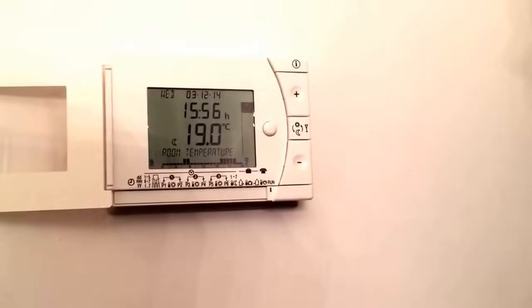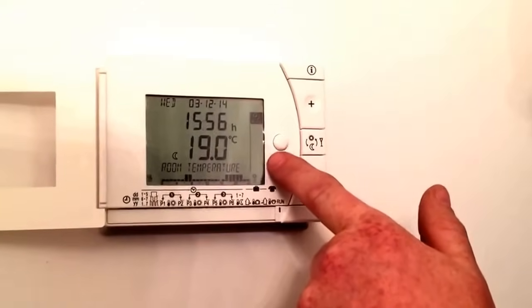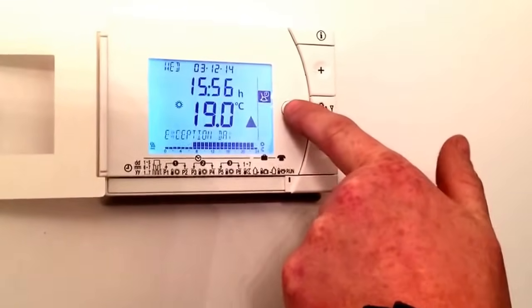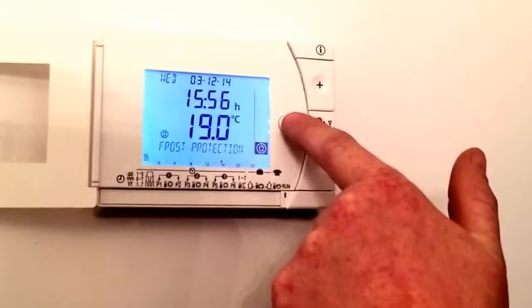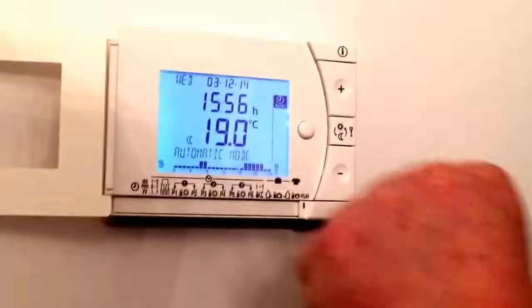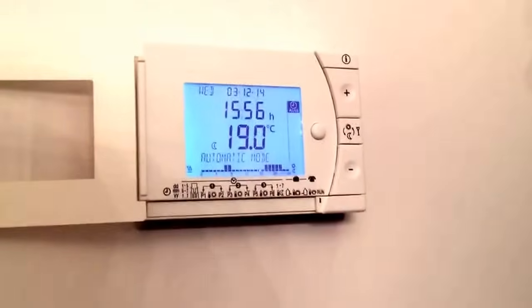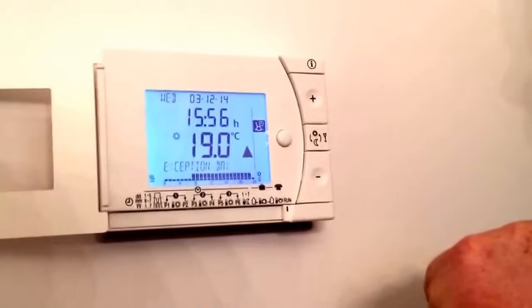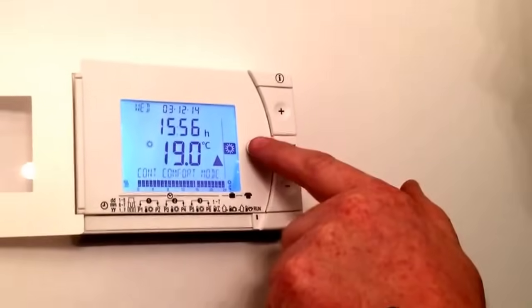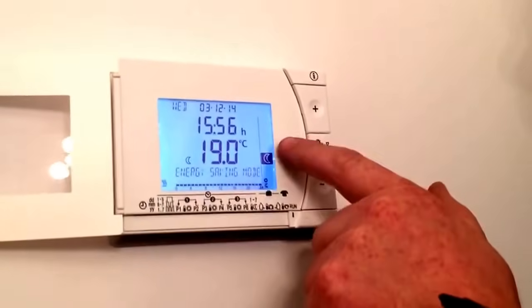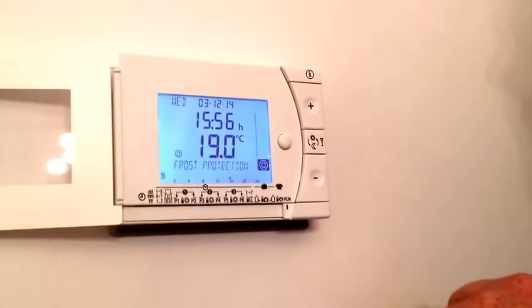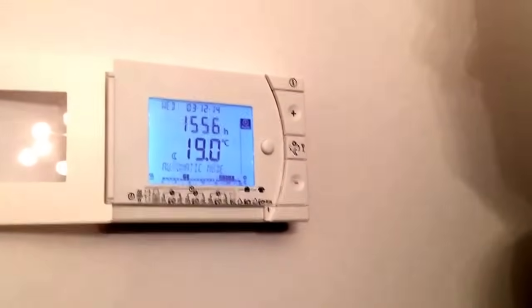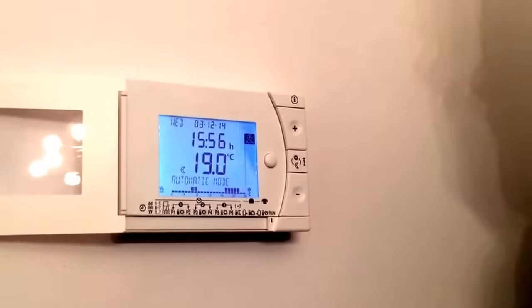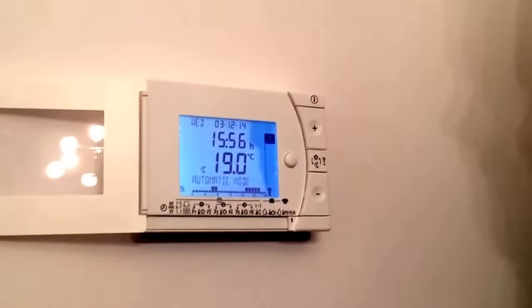Down this side, the main settings where we'll start is there are five different modes that we can have this time clock, programmable room stat, sorry, set up in. Top one, auto. The second, exception day. You have continuous comfort, or continually on. Energy saving mode, and we have frost protection. I'll explain each of those in a little bit more detail shortly. What we'll do though firstly is start with auto and show you how to set this time clock up.